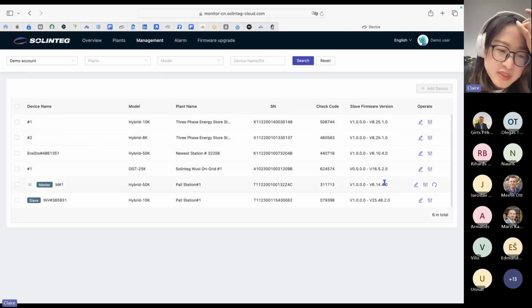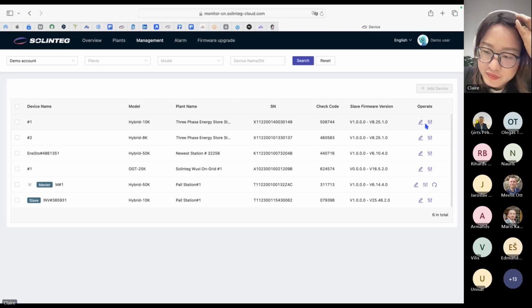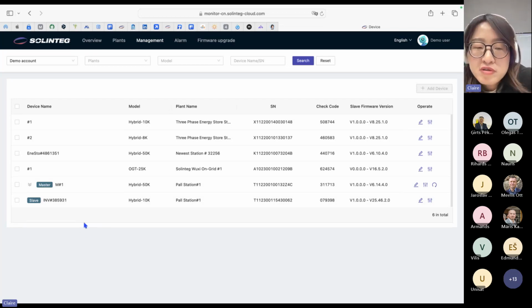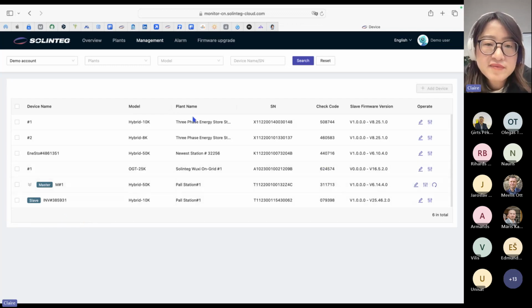Usually for device management, we just need to edit the device name, or set the device as a master or slave in the paralleling situation, because we support master-slave paralleling connection. So in that case, you must set one inverter as master and the others as slaves. So you have to set it here.